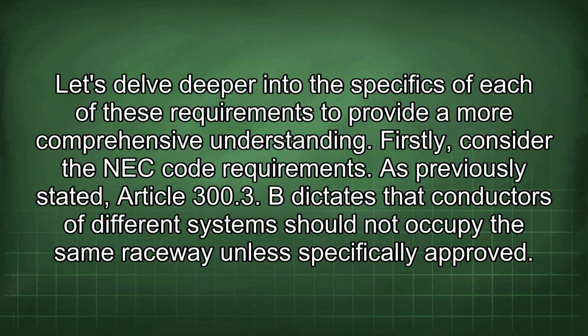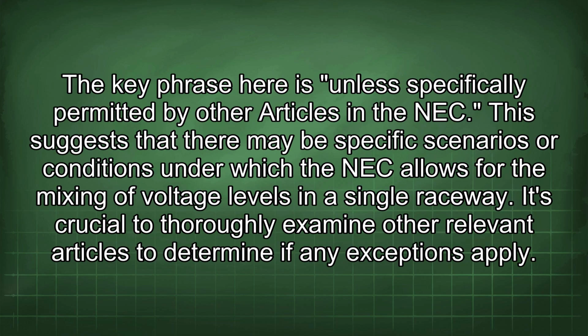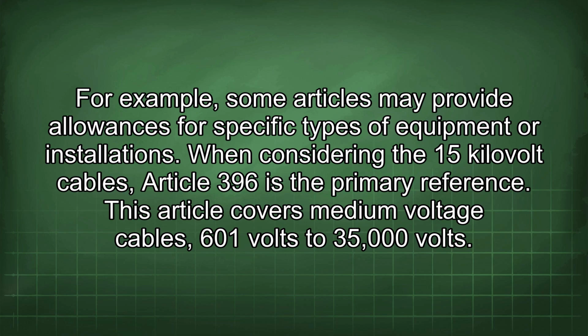Firstly, consider the NEC code requirements. As previously stated, Article 300.3 B dictates that conductors of different systems should not occupy the same raceway unless specifically approved. The key phrase here is unless specifically permitted by other articles in the NEC. This suggests that there may be specific scenarios or conditions under which the NEC allows for the mixing of voltage levels in a single raceway. It's crucial to thoroughly examine other relevant articles to determine if any exceptions apply. For example, some articles may provide allowances for specific types of equipment or installations.